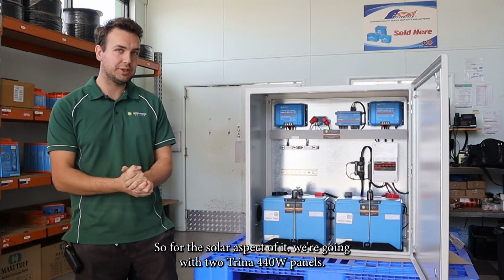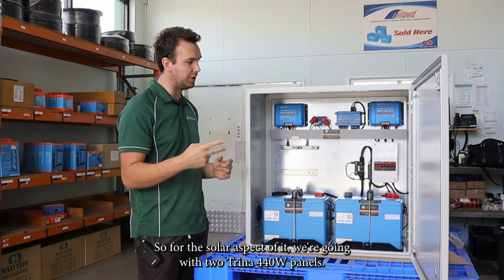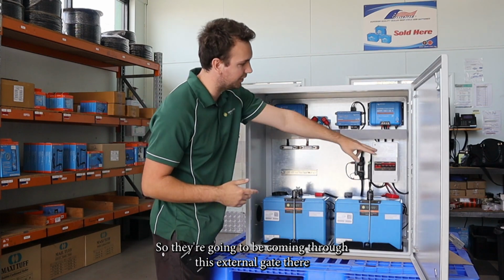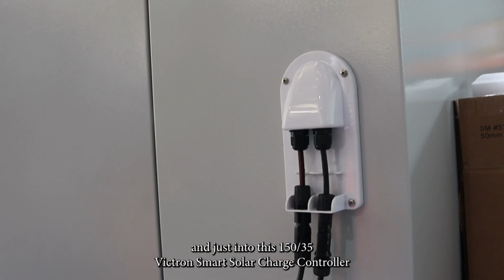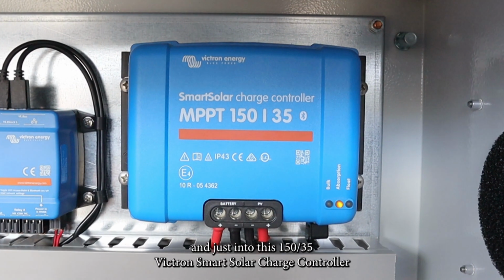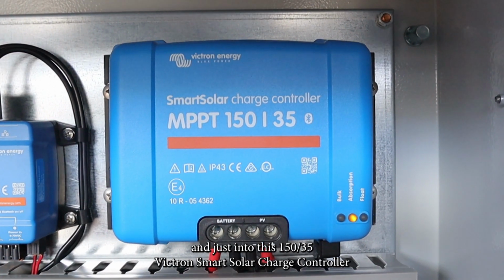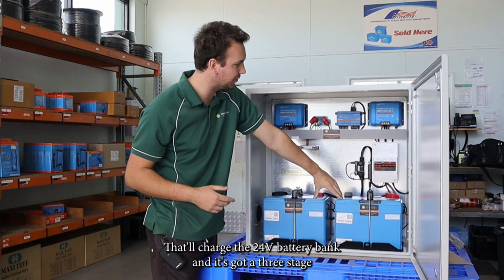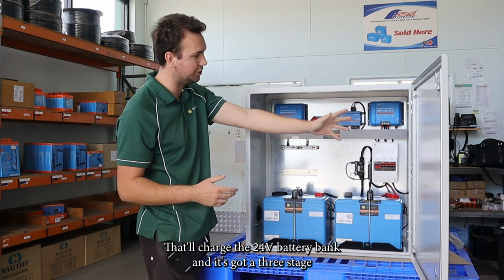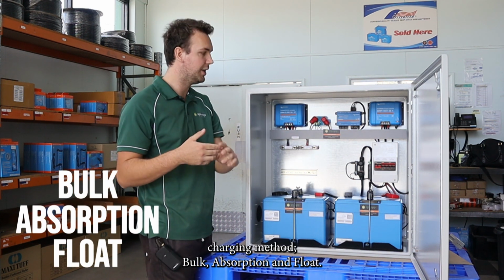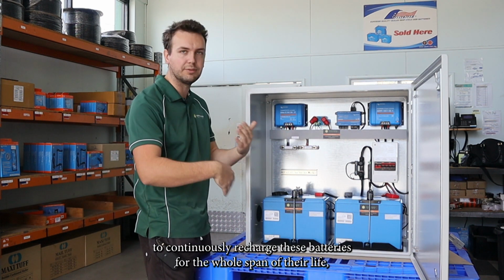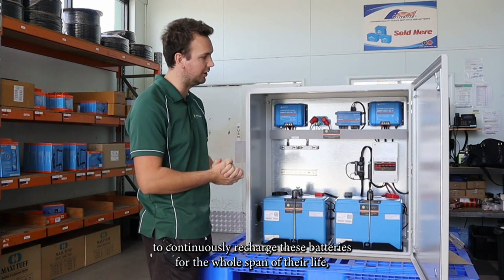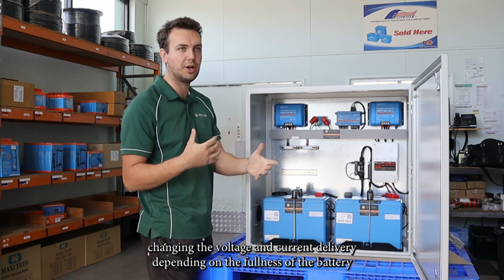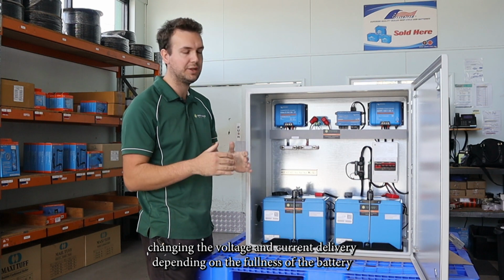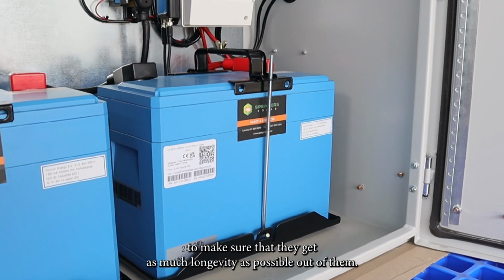For the solar aspect, we're going with 2 Trina 440-watt panels. They'll come through this external gland and into this 150/35 Victron SmartSolar charge controller, which charges the 24-volt battery bank with a 3-stage charging method: bulk, absorption, and float. It's perfectly happy to continuously recharge these batteries for their whole life span, changing voltage and current delivery depending on fullness to maximize longevity.